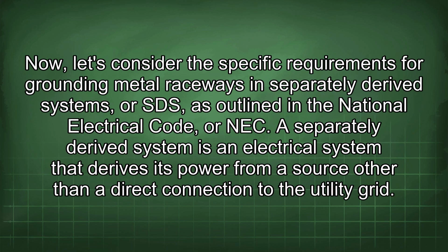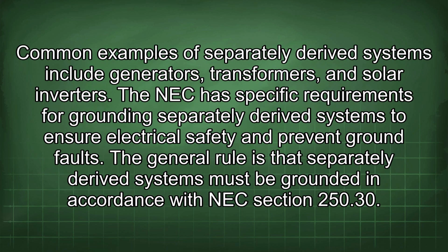Now, let's consider the specific requirements for grounding metal raceways in separately derived systems, or SDS, as outlined in the National Electrical Code, or NEC. A separately derived system is an electrical system that derives its power from a source other than a direct connection to the utility grid. Common examples of separately derived systems include generators, transformers, and solar inverters. The NEC has specific requirements for grounding separately derived systems to ensure electrical safety and prevent ground faults. The general rule is that separately derived systems must be grounded in accordance with NEC section 250.30.